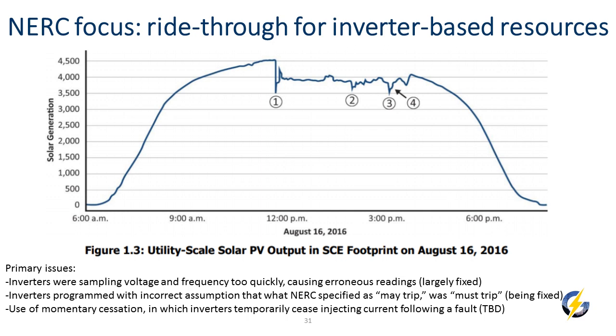So for the last 2 years, a little more than that now, they've been doing a lot of work on inverter-based resources. A little bit on the technical side: some of it was just the way the inverters were performing. They were reading frequency and voltage too quickly. They saw, for a few cycles, that the voltage or frequency appeared to drop drastically, so they concluded the system was way out of bounds, that voltage or frequency had exceeded the thresholds they're supposed to stay on for, and then dropped the resource. That was actually not the case. Those were erroneous readings as the system swung around. So that was part of the problem. You also had some issues with the PRC 24 standard. I'll talk about that in a minute, but people were misinterpreting it.